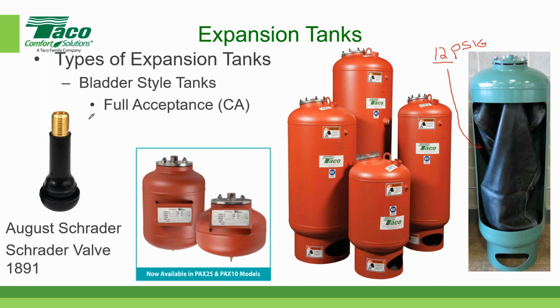you can go down to AutoZone or O'Reilly's. You can buy a hand pressure gauge. I think they're like $5. And if you put a pressure gauge on there and it doesn't read 12 pounds when it gets to the job site, then either someone bled the air out by pushing the little stem on the top of the valve, or there's a leak. But if it's done properly and it's got the 12 pounds, there won't be anything inside that bladder.